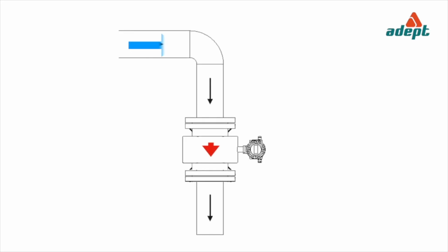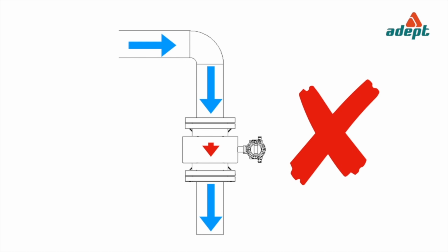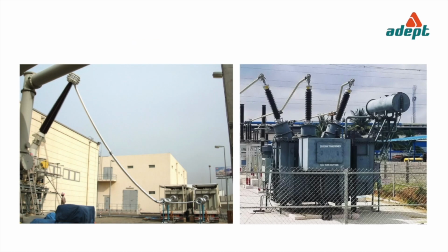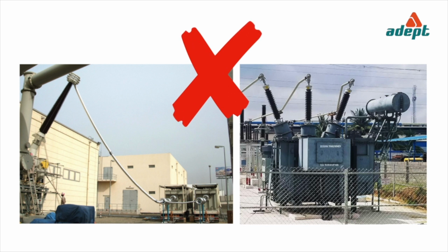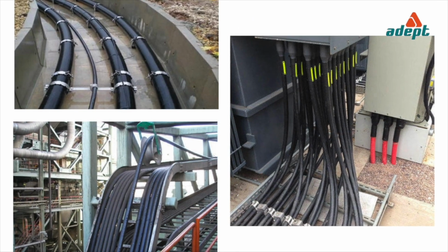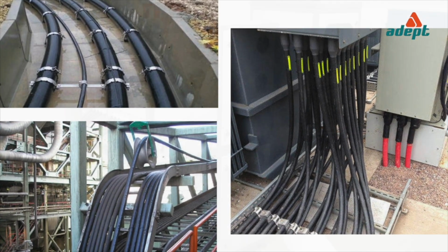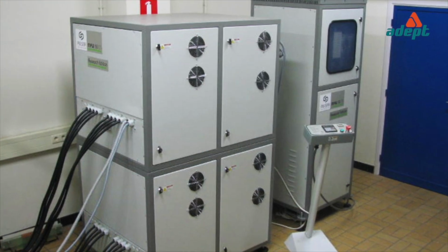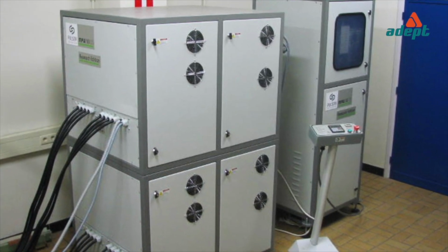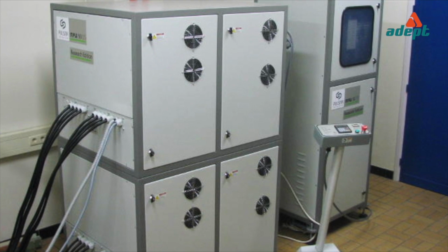Never install the flow tube in vertical pipelines with the liquid flow in the downward direction. Do not install a flow meter in close proximity to heavy electrical equipment, power transformers, HT and LT power cables, and sources of powerful electromagnetic radiation.